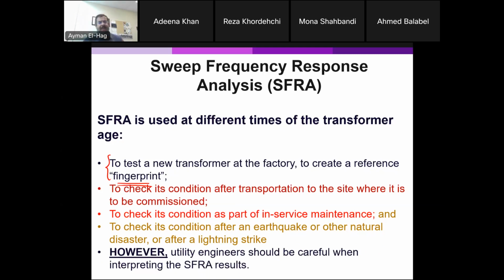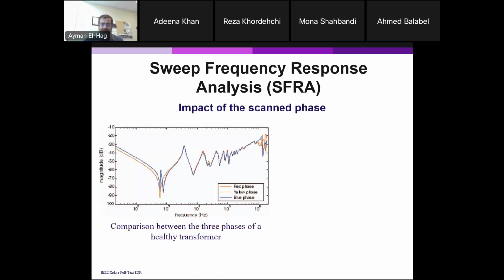I will give you just two examples here. The first example is the SFRA for the three phases. One of you, if I recall, mentioned that the middle phase has a different signature than the red and the blue. Now, red, yellow, blue is exactly the A, B, C phases, or the U, V, W. Here in North America it is A, B, C, and the IEC, sometimes the British standard, uses red, yellow, blue. So we have different ways of calling the phases, but this is the middle phase.